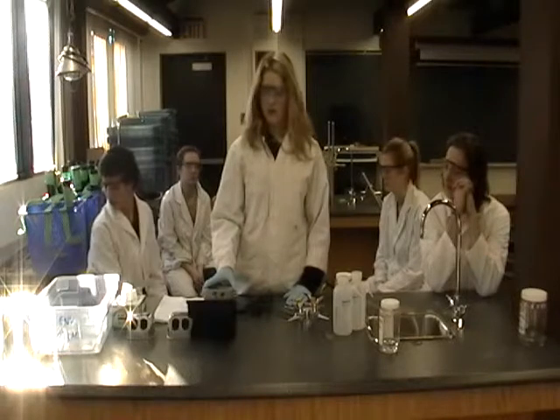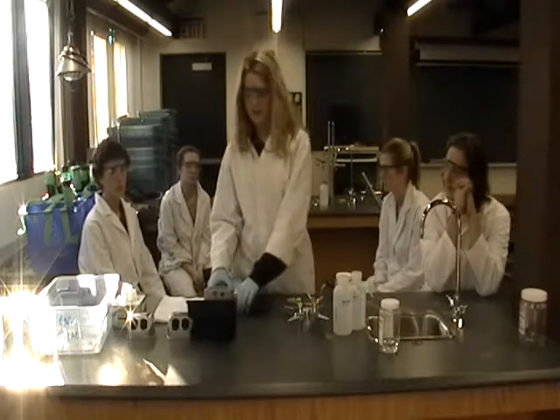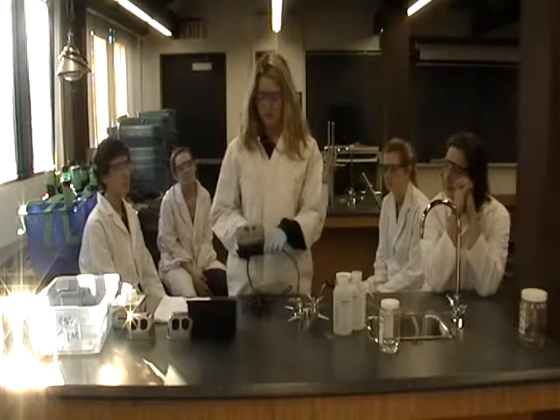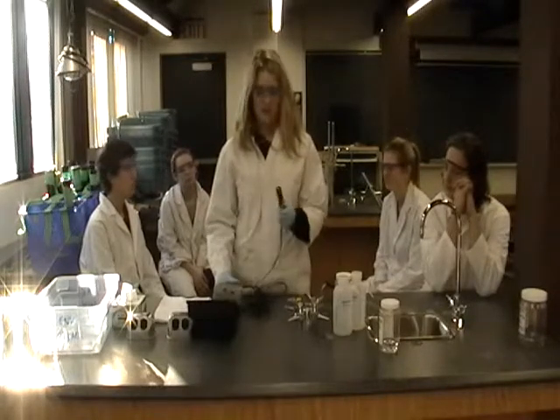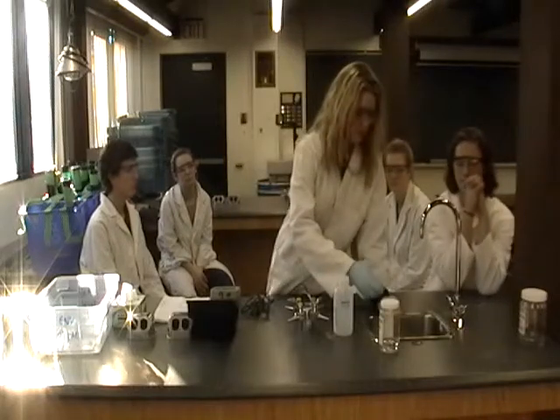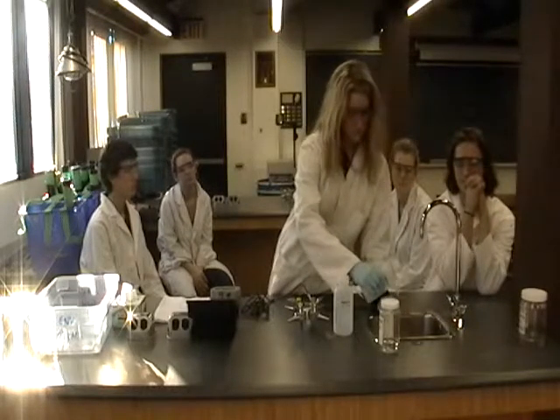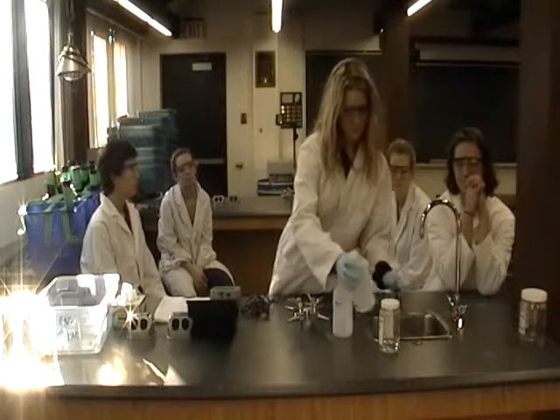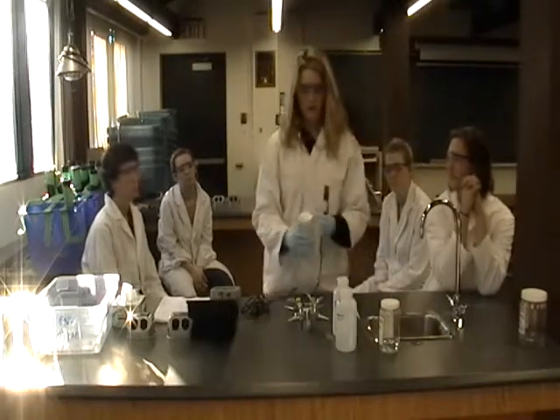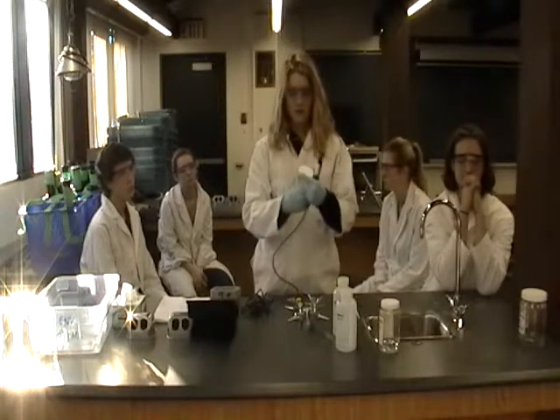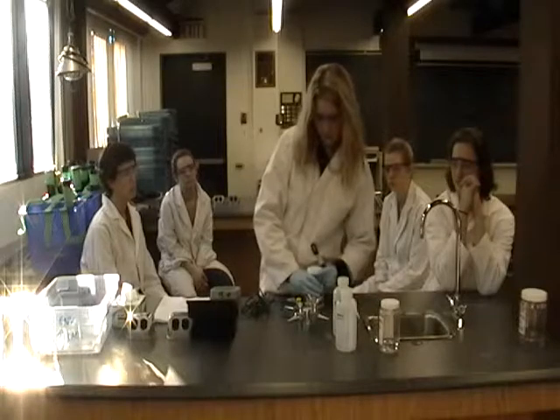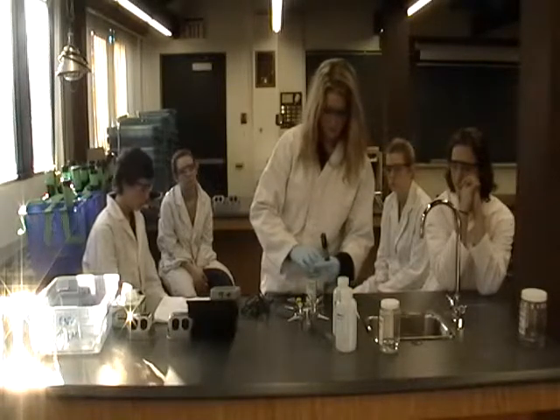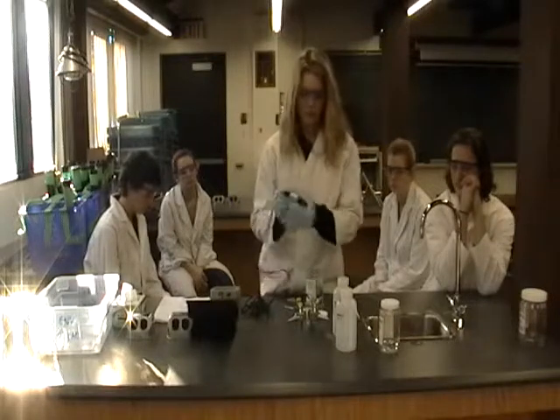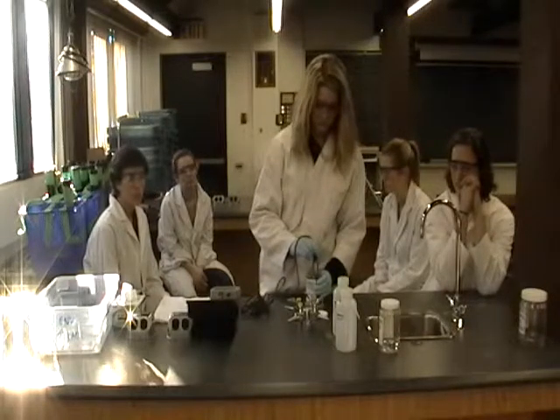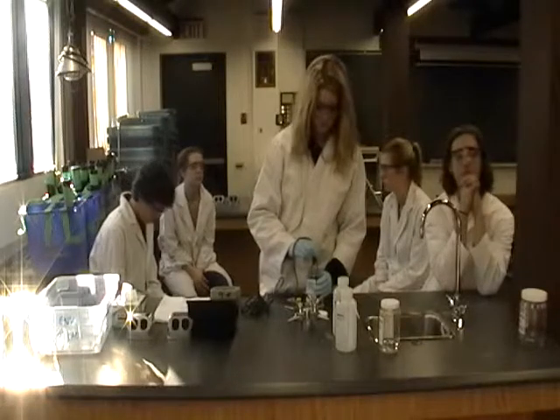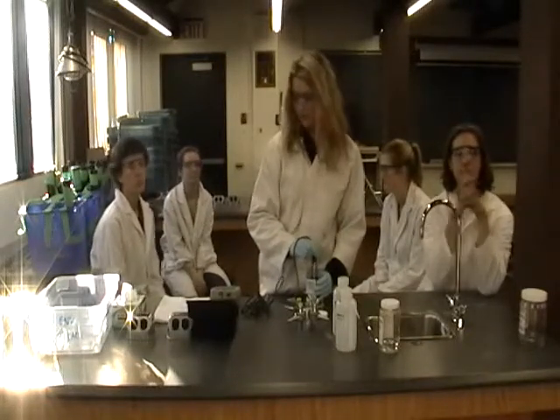Okay, now that you've gotten your readings from the titration kit, you're going to want to take out the dissolved oxygen meter and turn it on. And you're going to want to clean the probe with distilled water so as to not affect the reading. Then you're going to want to open the PET 500 with the sample water in it that has no air bubbles, because that would affect the reading also. You want to put the probe in there and just move it around for a few seconds to let the reading settle.